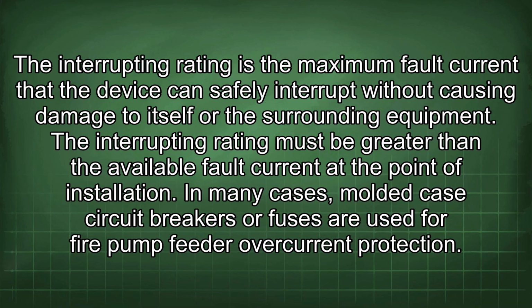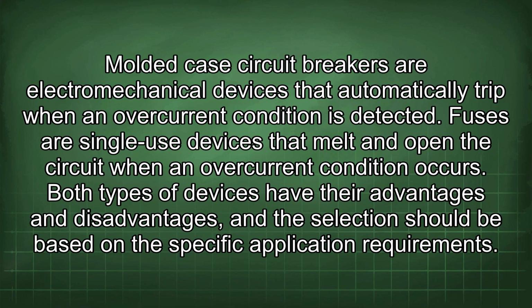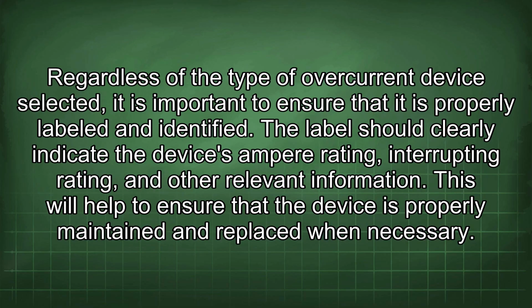In many cases, molded case circuit breakers or fuses are used for fire pump feeder overcurrent protection. Molded case circuit breakers are electromechanical devices that automatically trip when an overcurrent condition is detected. Fuses are single-use devices that melt and open the circuit when an overcurrent condition occurs. Both types of devices have their advantages and disadvantages, and the selection should be based on the specific application requirements. Regardless of the type of overcurrent device selected, it is important to ensure that it is properly labeled and identified. The label should clearly indicate the device's ampere rating, interrupting rating, and other relevant information. This will help to ensure that the device is properly maintained and replaced when necessary.